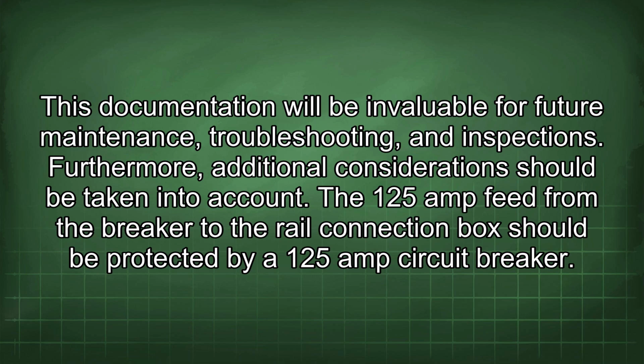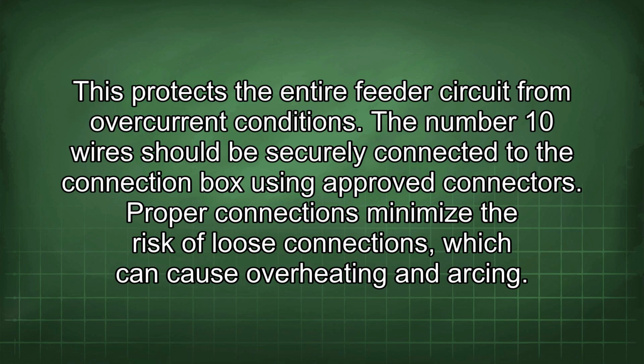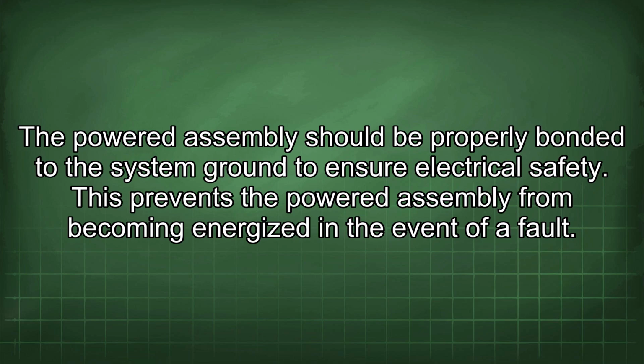Furthermore, additional considerations should be taken into account. The 125 amp feed from the breaker to the rail connection box should be protected by a 125 amp circuit breaker. This protects the entire feeder circuit from overcurrent conditions. The number 10 wires should be securely connected to the connection box using approved connectors. Proper connections minimize the risk of loose connections, which can cause overheating and arcing. The powered assembly should be properly bonded to the system ground to ensure electrical safety. This prevents the powered assembly from becoming energized in the event of a fault.